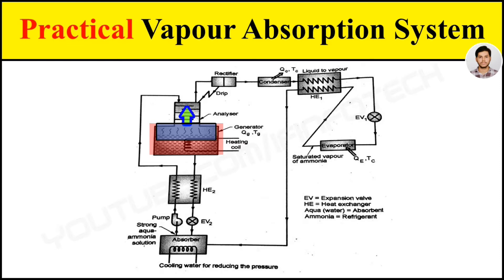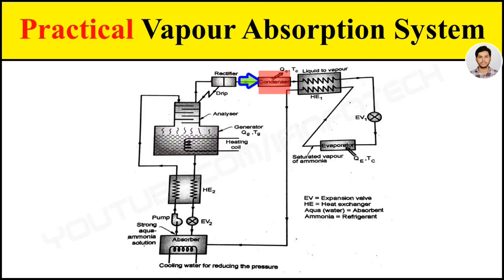This vapor passes through the analyzer where dehydration of the aqua ammonia takes place to produce strong ammonia vapor. If dehydration is not complete, the water particles are separated in the rectifier and the water is sent back to the generator. The strong ammonia vapor then passes through the condenser, while a weak aqua ammonia solution forms in the generator.